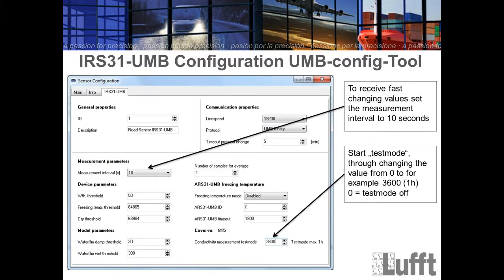That's the theory. You have to open the UMB configuration menu for the IRS31, and you see it here. You have two things which you can change here. First of all, the measurement parameters for the measurement interval. You can go down to 10 seconds if you want, so you will get fast changing values, so that you don't have to wait so much. That's what you can do with the interval here.